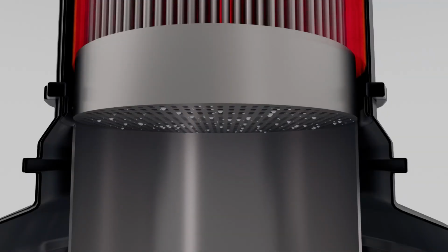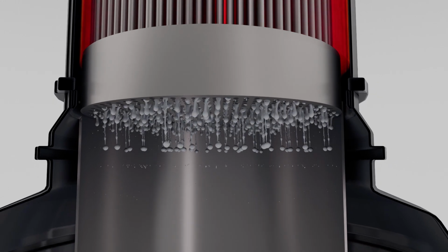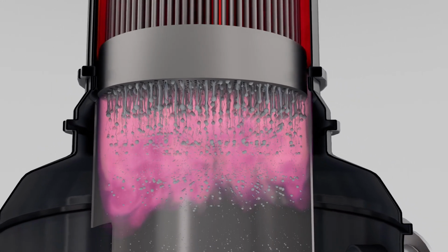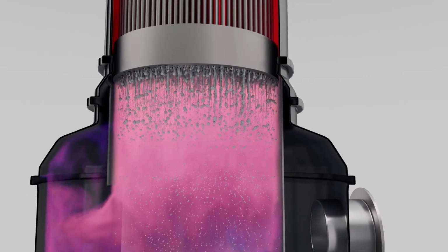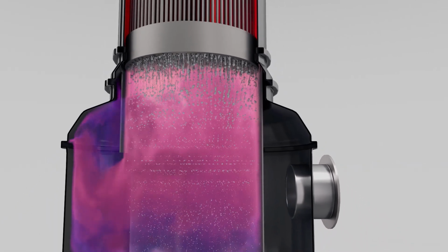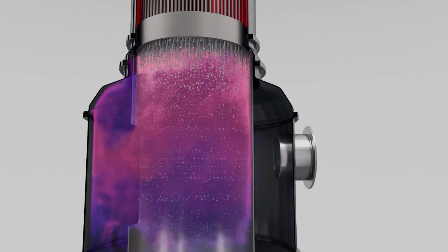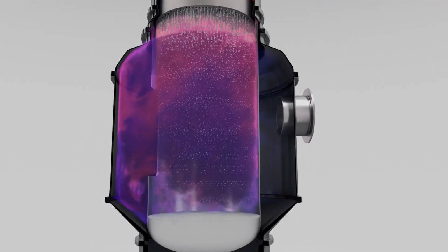It condenses on the outer walls of the tube bundle and transfers its thermal energy onto the tube. The liquid on the inside of the tube bundle absorbs this heat and starts to boil. Parts of the product separate in the form of water vapor, and the product concentrates along the tube. At the lower end of the tube bundle, the concentrated product enters the so-called separator. This is where the vapor that develops is separated from the concentrate. The concentrate drops down and collects in the dished boiler head. From here, it's pumped out for further processing.